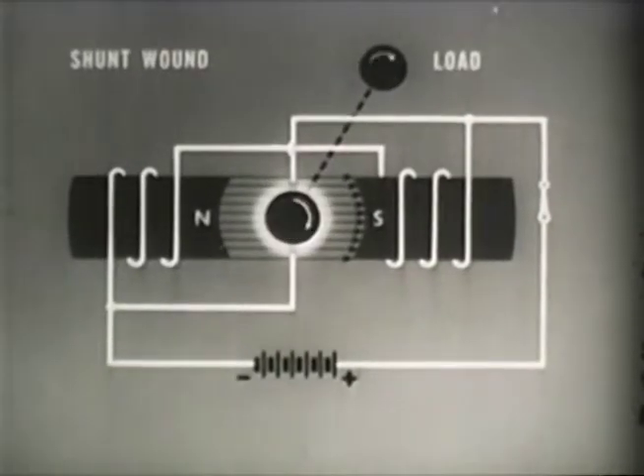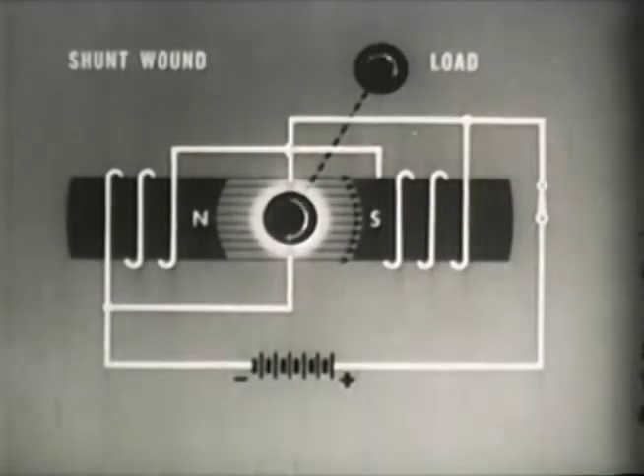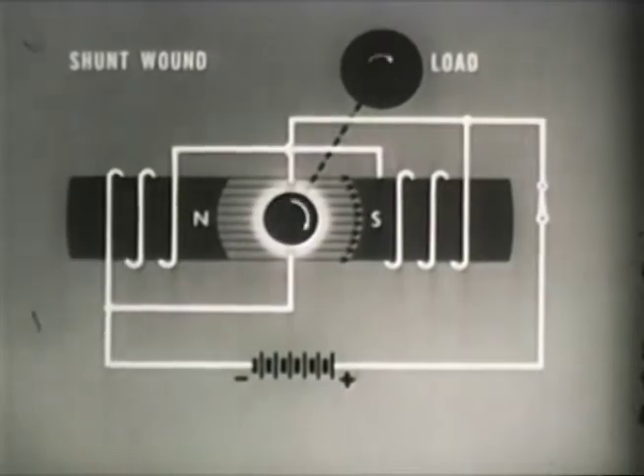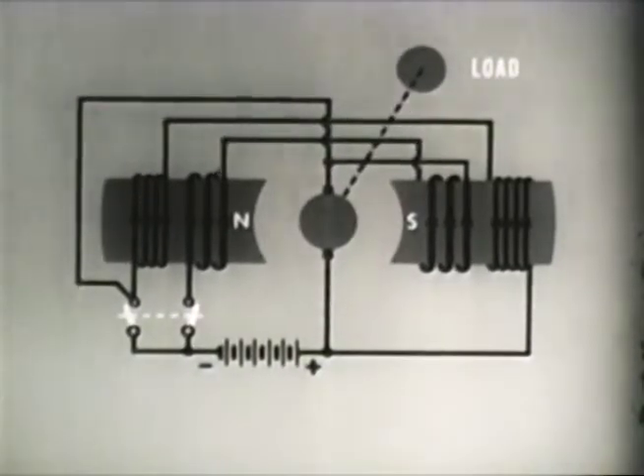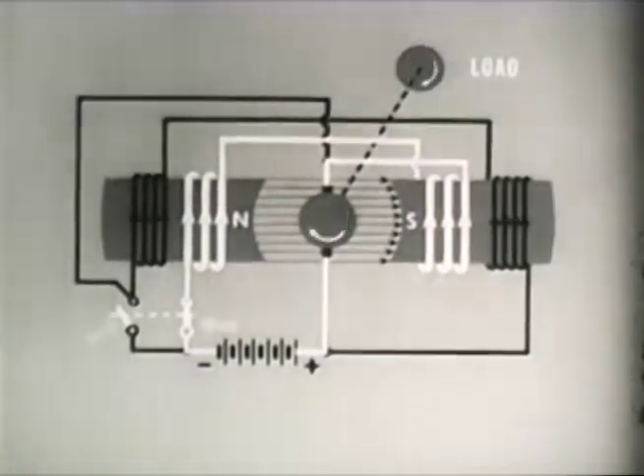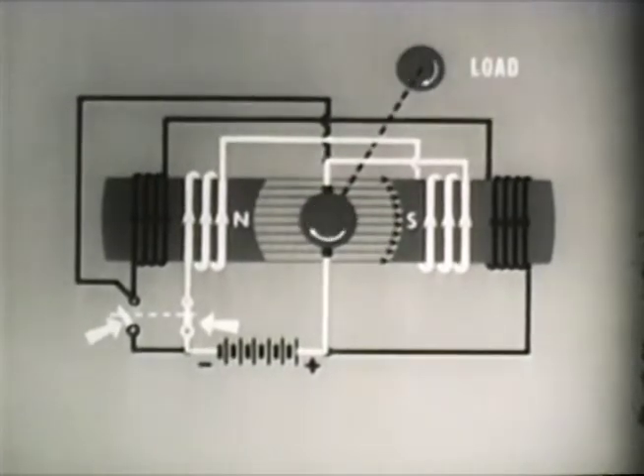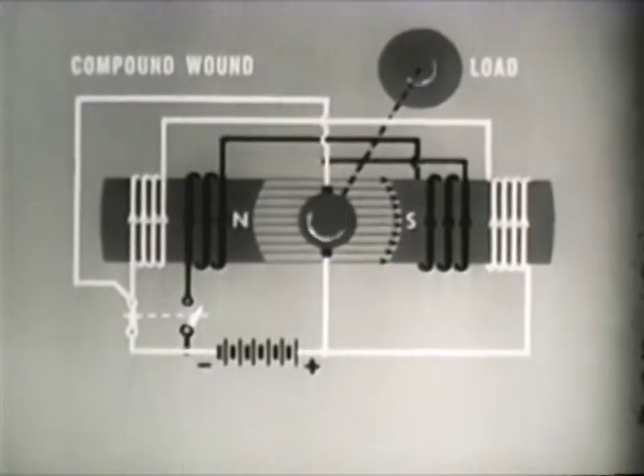In shunt wound motors, with the field coils connected in parallel across the DC input terminals, the starting torque is not too good. But since the field current is independent of the rotor current, the speed regulation is quite good. The compound wound motor combines the best features of both types: it uses a series section for good starting torque, then switches to a shunt arrangement for good speed regulation. DC electrical motors and generators are at the heart of much military equipment, and a proper understanding of them is therefore important.